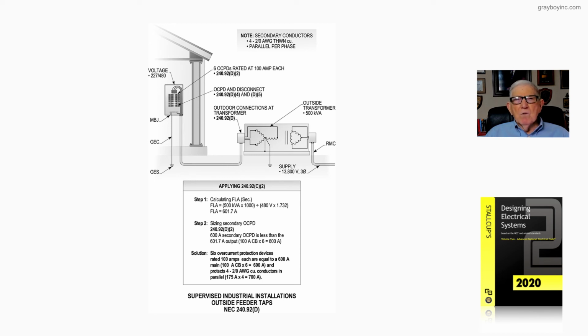Instead of having single conductors per phase, we have 4 2-aughts per phase at 175 amps each, and then the 600 amp protective device main, or 6 100s would give us 600 amps. We've protected the output of the transformer plus the ampacity of the conductors, and that's what our figure 20-43A is illustrating.